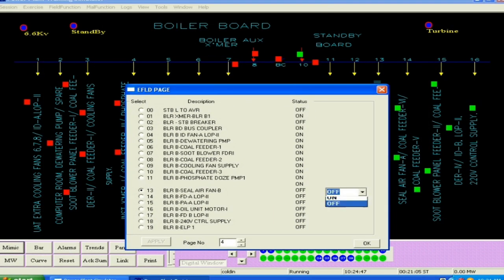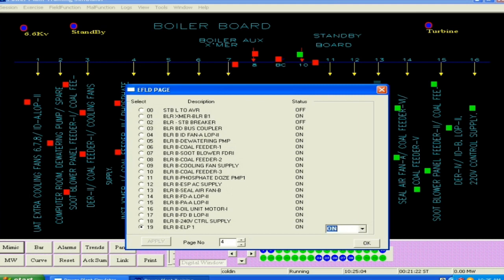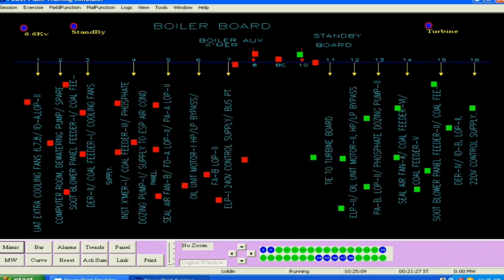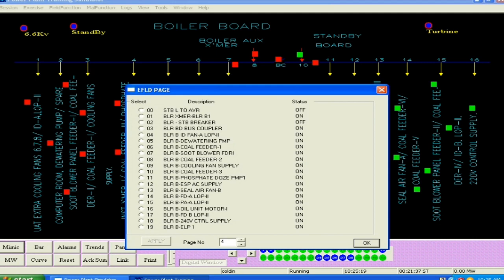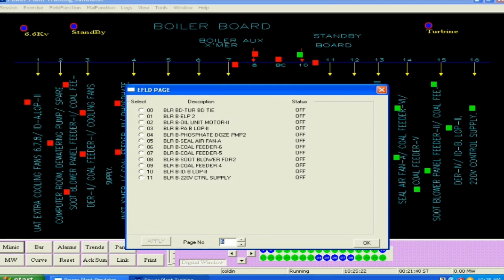So on page number 4, till 19, and also some auxiliaries on page number 5. After completing page number 4, we can go to page number 5 for the remaining ones. Now there is a tie from the boiler board to the turbine board. The turbine board is charged from the boiler board itself. So that tie is there. That tie you have to make on. That is index number 00 on page number 5.